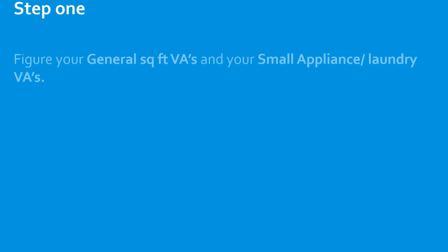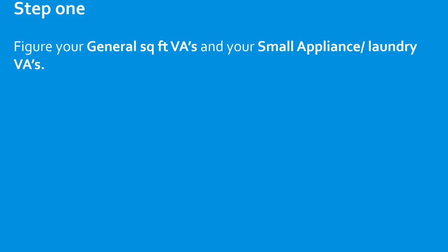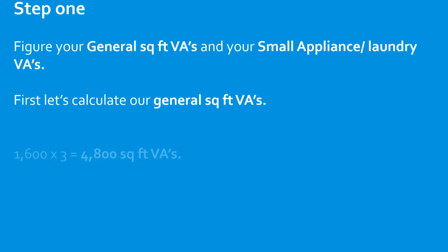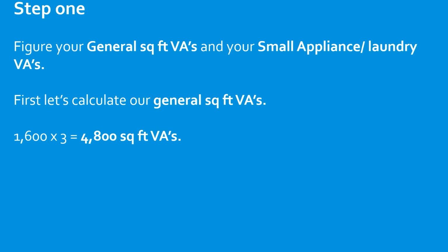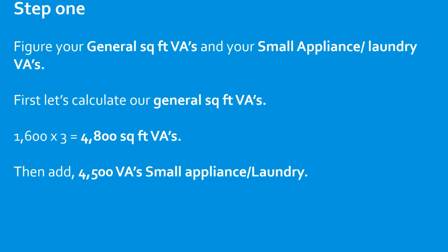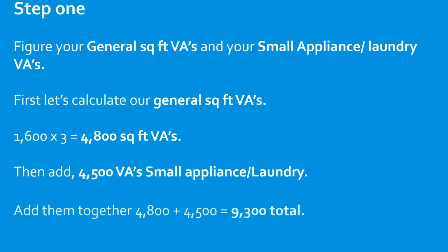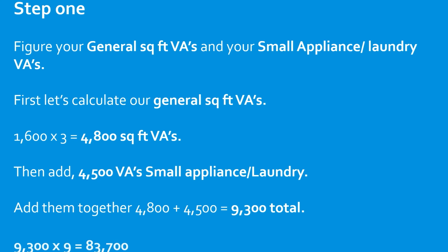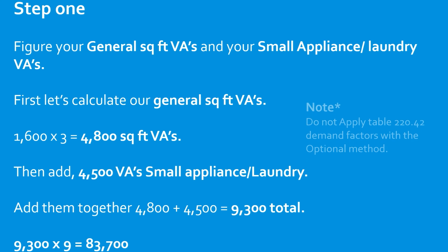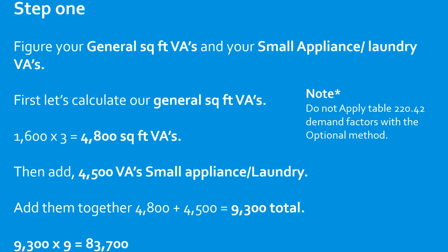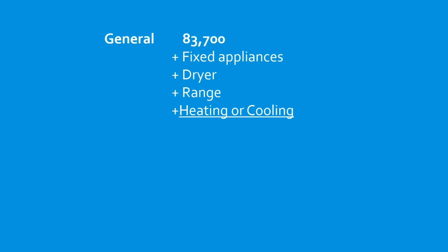It's just like doing a single dwelling unit, just multiplied by 9. So get your general and your small appliance laundry first. 4,800 square foot VAs. Get your small appliance and laundry in there. Add them together. Now just multiply it by however many apartments you're doing. In this case, it's going to be 83,700 VAs. Note, you do not use the tables in 220.42. We're going to apply a demand factor at the end.